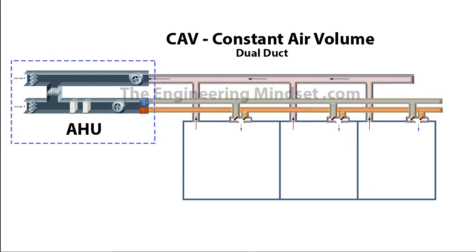Another option you might see in industry is the dual duct CAV system, which is becoming more and more uncommon — you'll still find it in some older buildings. Basically you've got two ducts supplying the room: one provides cold air and the other supplies warm air. This air is then mixed in dampers in a box to suit the temperature inside, and the return air is returned back in a normal duct to be recycled or dispersed to atmosphere. This system gives much improved thermal control but there is little control of humidity. It's also not particularly energy efficient, as you're supplying air through two streams with all that resistance for the fan to overcome, and you're unnecessarily heating and cooling air that may be mixed and then have the load change.